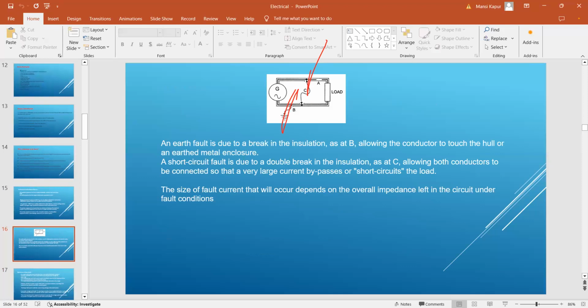An earth fault is due to a break in the insulation. So if there is a break in insulation, there can be an earth fault, right? Now this insulation break can occur anywhere, as at B, allowing the conductor to touch the hull. Can you see at B? Now it is touching the hull or an earthed metal enclosure. A short circuit fault is due to a double break in the insulation. So a short circuit will only occur when there is one more earth fault, because this is an insulated system, right? Yes, sir. So with a single wire, there is no potential difference generated, right? So it is not doing any harm.